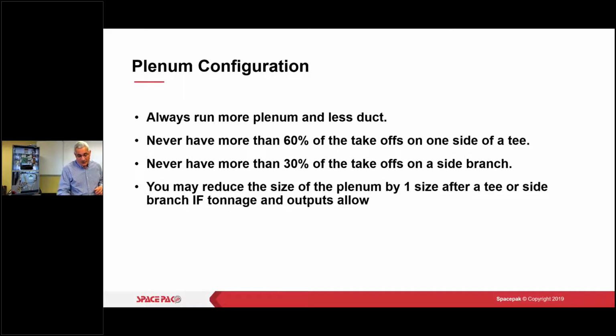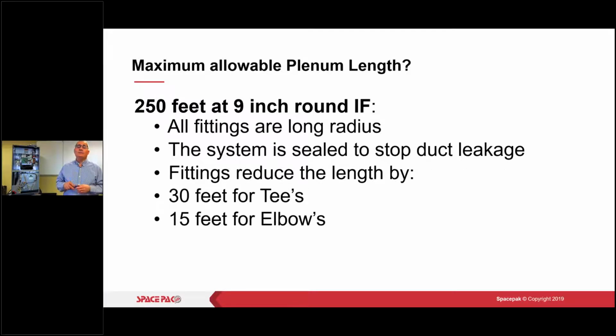We've been asked on older systems that maybe had the 7-inch type plenum, can I just adapt my J series currently to that? And the answer is yes, but you have to come off of our current air handler with 9-inch. You have to come off with 9-inch and make it an ample amount of 9-inch plenum as much as you can before you adapt to the smaller size. It's always best practice to really abandon the old plenum and just run new. All right, the 9-inch, 64 square inch is really your best plenum design. So I can go up to 250 feet of 9-inch, if all the fittings are nice long radius, as you can see, everything is sealed. So if you're using our spiral vent, that's what you want to do. We end up reducing if we put a lot of elbows and T's in. So every T is worth 30 feet and every elbow is worth 15 feet.